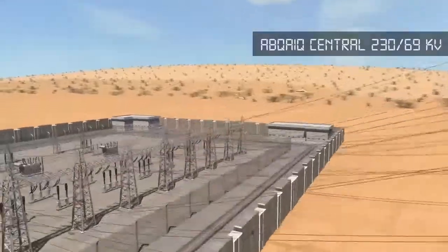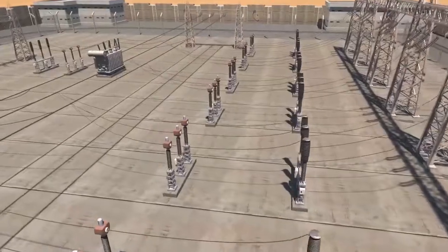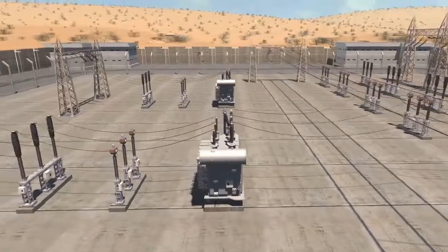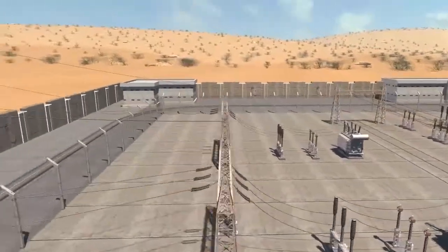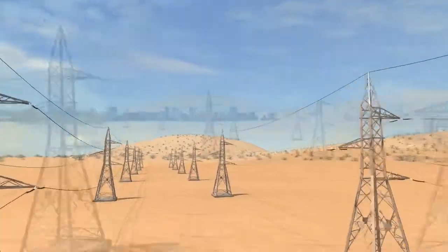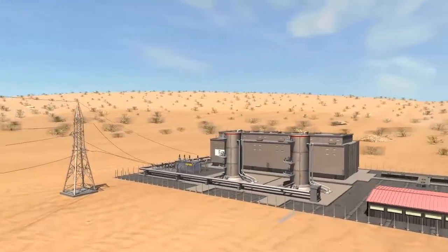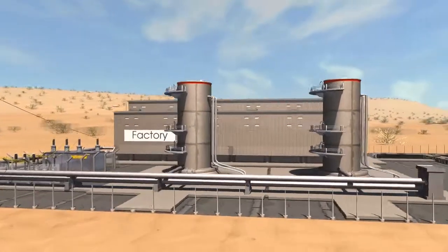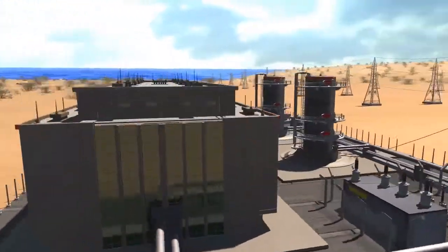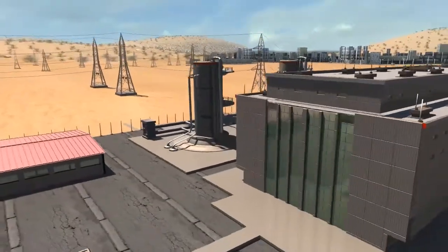The grid station receives 115 kV or 69 kV electrical energy through cables and steps it down to 13.8 kV. Grid stations, which are located inside cities, are considered the final link in the transmission network. For higher consumption level consumers such as factories and trading centers, the supplied power may be at high voltage levels such as 69 kV or 13.8 kV, through specific substations with a suitable power size.